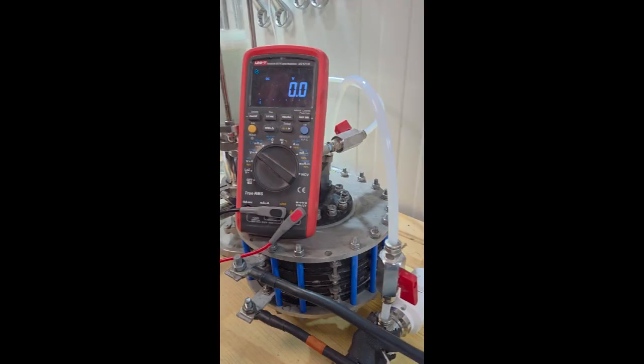During operation, we monitor the voltage differences between the individual cells. For this test, the total system voltage is set to a round reference value, which in this case is 8 volts. This makes it easier to sum and verify the values measured across the cells. Each cell should operate at 2 volts if no leakage current is present. It can be clearly seen that all cells are operating perfectly within the same working range.